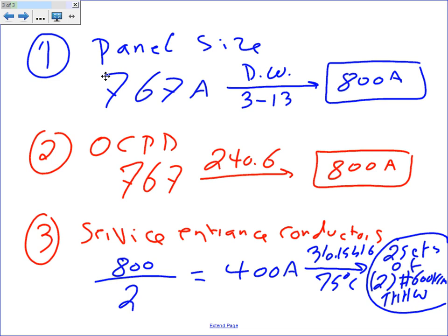So use this: 400 amp, 500 kcmil. If you go higher amp or higher than 500 kcmil, most likely parallel, with some little exception if you're hovering right at the 400 or right at the 600 kcmil. Can we do the service?